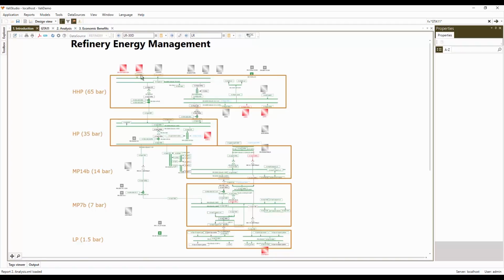The utility system includes two cogen units which produce electricity and high pressure steam, one boiler producing steam, and 3 turbo generators producing electricity and consuming high pressure steam. This is not an obvious system to run and to optimize, which is why the customer has put in place an optimizer, which is recommending actions to minimize the fuel and overall energy costs of running the system while satisfying the utility demand from the refinery process units.